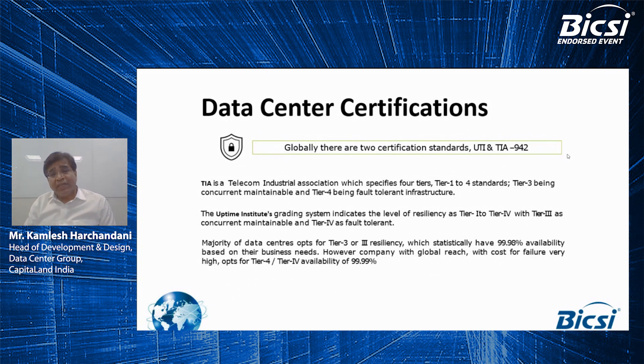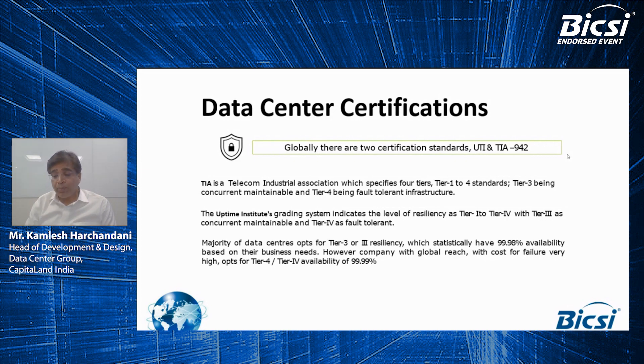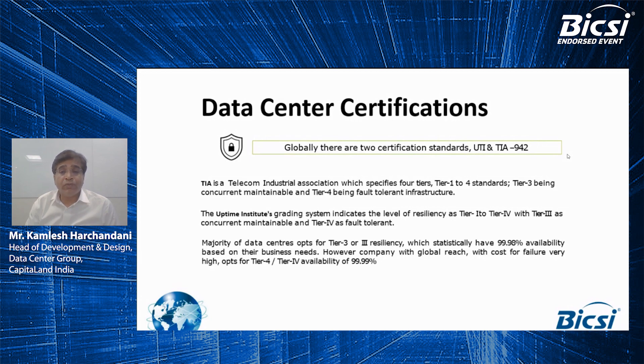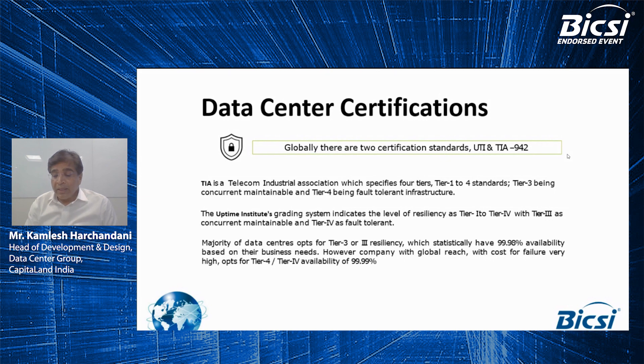Globally there are two certification standards followed: Uptime Institute and TIA 942. CapitaLand data centers go for either certification. However, very few colo service providers opt for any certification in recent times. If I talk about Tier 3, it is almost the same for both — concurrent maintainability. The major difference between the two is the redundancy level for Tier 4 requirements: TIA 942 says a 2N configuration is required for every equipment, whereas Uptime says it can be N+1 configuration with fault-tolerant design. That's the major difference between the two.